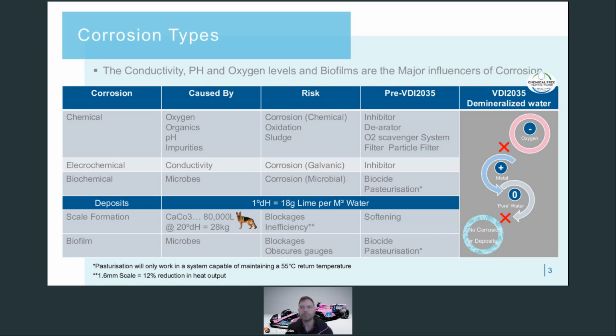Thirdly, biochemical corrosion happens where microbes excrete chemicals that corrode the materials they live on. They can be killed through pasteurization, but this is difficult to achieve in modern systems, and so biocide is frequently used. This is not a good idea. Biocide is a killer chemical. Demineralized water, on the other hand, doesn't have any mineral building blocks that the bacteria need to grow. And so it's a much safer route to inhibit biochemical corrosion.